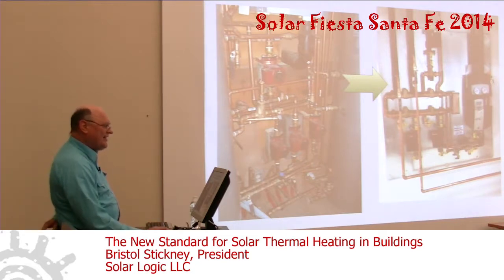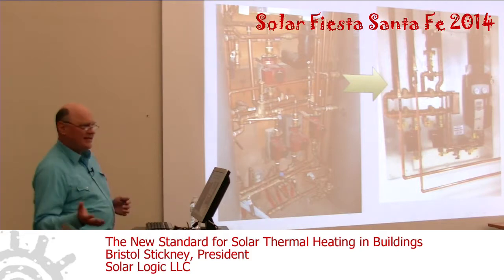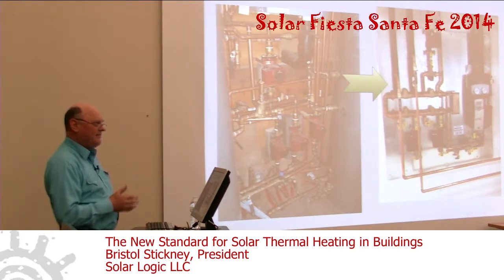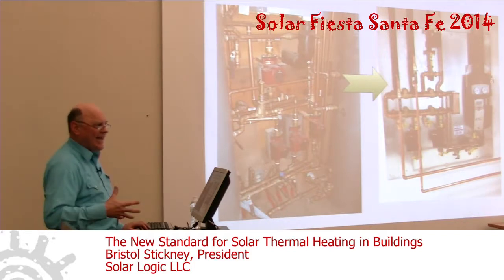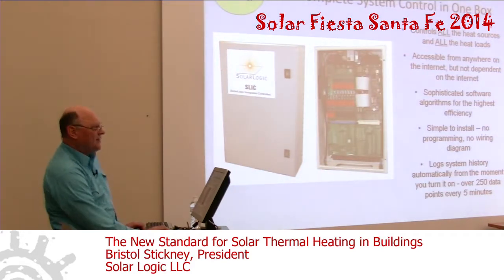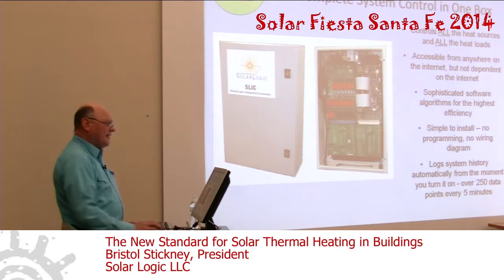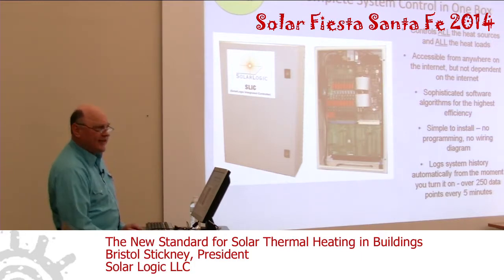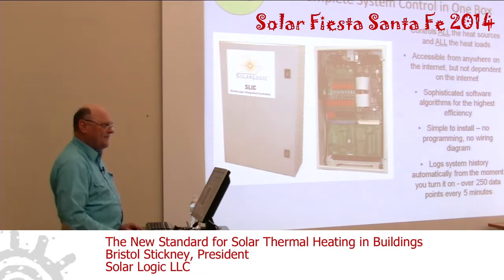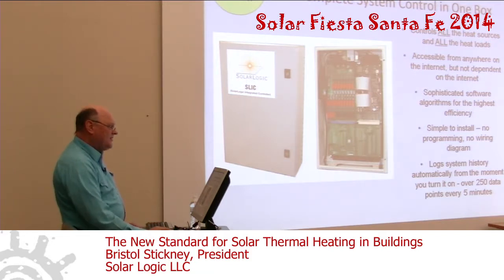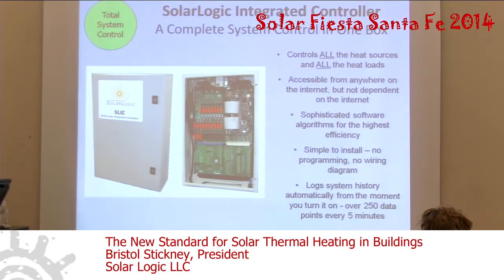And if you follow the new standard, then all of a sudden the controls are already done for you. If you follow this standard, you don't have to reinvent the controls. The controls come in a package for you, and they're guaranteed to work together. So here's what the controls look like. This is something that's invented, patented, and manufactured here in Santa Fe by Solar Logic. And what you see is a computer that controls the whole heating system, little orange relays that are used to turn the pumps on and off, and they're under computer control, so the computer can turn anything in the system on or off through one of those little orange relays.